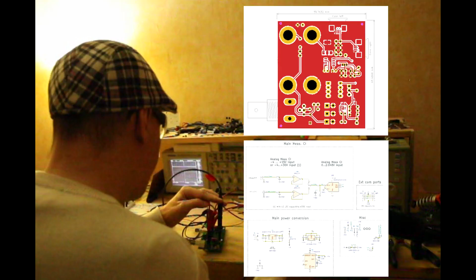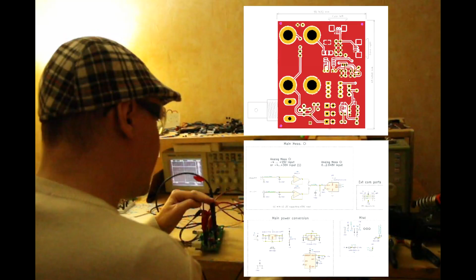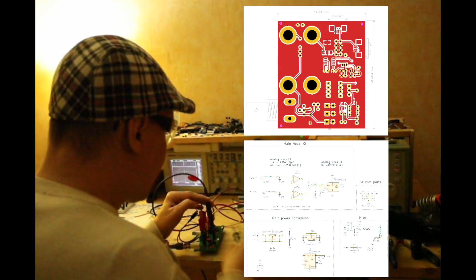We have a non-inverting op-amp stage at the input, so we have a high impedance, and therefore we don't have any divider, so it doesn't matter what is the impedance and what is the tolerance on this impedance on the probe, because we are measuring without any current, so we have a high impedance input. And let's check, for example, the second board, now just power supply, and I'm checking the 10 volts ref on the second board. And we can see that the output is reading also 10.1 volts. And so the advantage of this setup is that now this oscilloscope probe is presenting a high impedance to the circuits that we are measuring. And we are measuring this 10.1 volts.